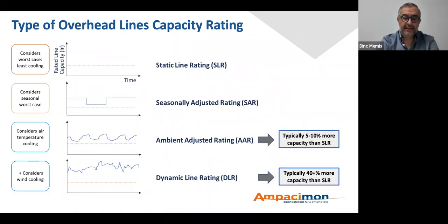We can split line capacity rating measurement mainly into two categories. One is direct measurement and the other is indirect measurement. The first three types you see on this slide reflect the indirect measurement methods, which in a nutshell use weather stations and modeling. The first one is static line rating, which is the most conservative line rating, considering the worst case scenario. The second one is the seasonal rating, which applies a static line rating defined by seasonal impact rather than using a flat and constant line rating throughout the year.